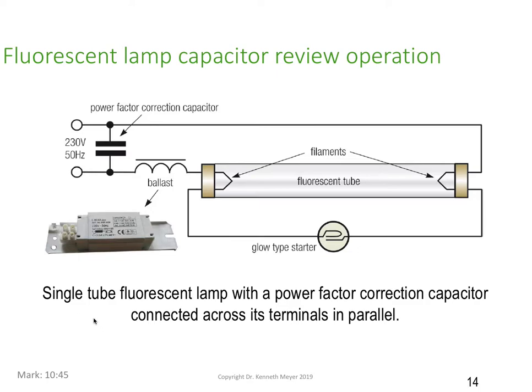So there you have it. That's why we have to add a capacitor into our fluorescent light fittings, but it only applies to fluorescent tubes. And as the technology of LED lighting starts to displace fluorescent tubes, there'll be less and less of these ballasts being used. Therefore, there won't be any need for the capacitor to be added in those kinds of fittings.